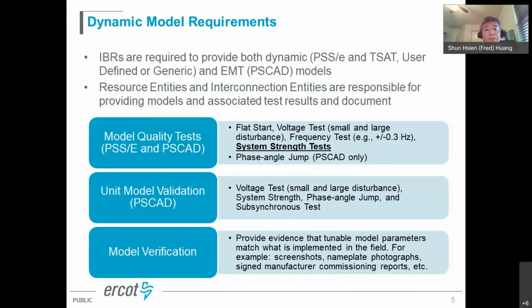From the weak grid perspective, we also require what we call a special test, where the model is tested under different system strength conditions from the short circuit ratio perspective, to examine model behavior under different short circuit ratios. We don't currently have a minimum system strength requirement, but this test provides very good insight into model behavior, especially under weak grid conditions.